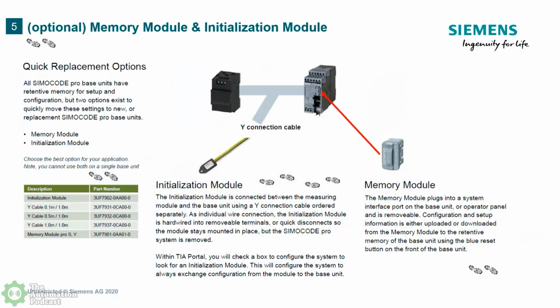So we have 3 main ways of programming them. And I'm going to just speak to it now as if they were already programmed and you're a maintenance guy going out and swapping one out because it's not pulling in the contactor, and maybe that contactor inside the SIMOCODE needs to be replaced. So once I've done the mechanical side of things of replacing it, it's DIN rail mountable. So you remove the cable for the CT, remove the terminal blocks, lift it off the DIN rail, grab the new one out of the box, remove its terminal blocks, snap it on the DIN rail, plug in the existing terminal blocks, plug in the CT, and mechanically it's ready to roll.